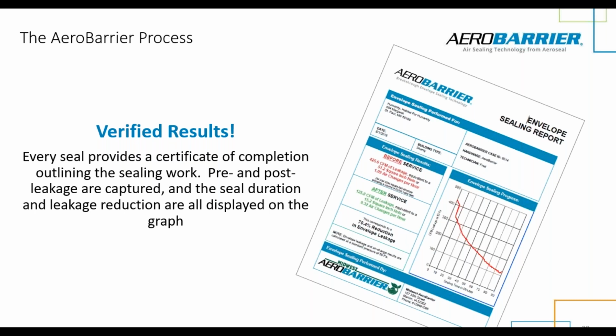The one thing to call out here is this is going to vary a little bit from what a final blower door test would read. Because we have things taped off and because of the prep that we do, some leakage is going to be reintroduced to the structure after we're done. So the difference between the final blower door test and us is really about the prep work. When you think of AeroBarrier, you can think of it more as an enclosure test. Because we're taping off the ductwork and the dampers aren't in place, because we're taping off fireplaces and some windows, that leakage is going to be reintroduced when we're done. And when you do a final blower door test, it's going to be an as-built test where the dampers are engaged, hopefully seated correctly. So there is going to be leakage reintroduced. The beauty of AeroBarrier is we can dial in that number.